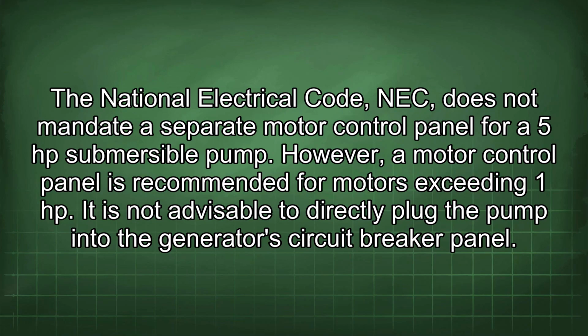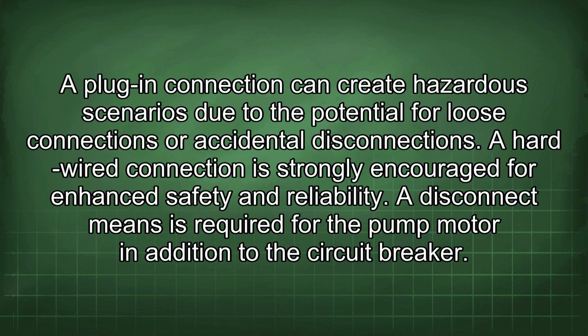The National Electrical Code (NEC) does not mandate a separate motor control panel for a 5 HP submersible pump. However, a motor control panel is recommended for motors exceeding 1 HP. It is not advisable to directly plug the pump into the generator's circuit breaker panel. A plug-in connection can create hazardous scenarios due to the potential for loose connections or accidental disconnections. A hardwired connection is strongly encouraged for enhanced safety and reliability.